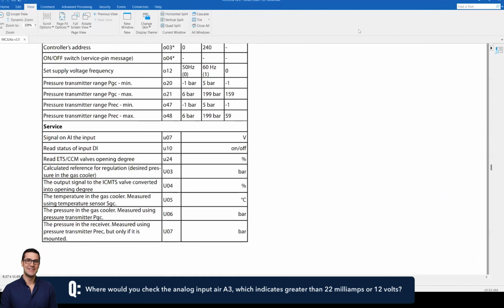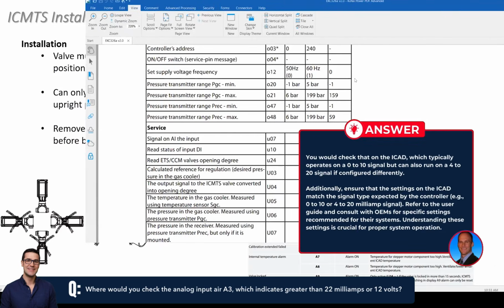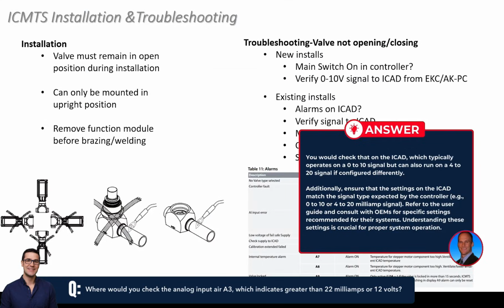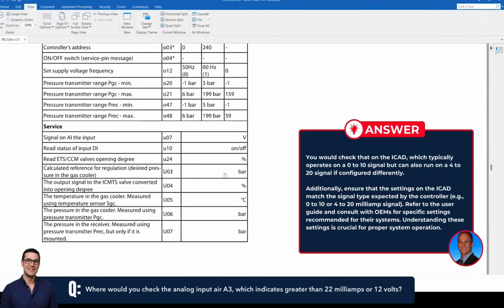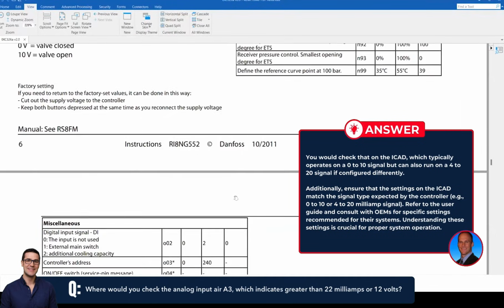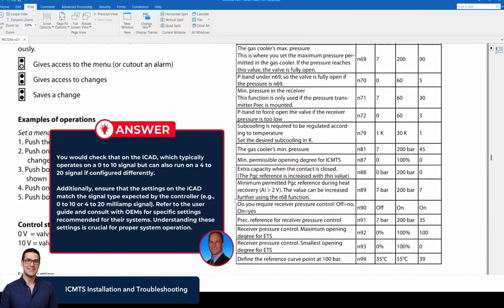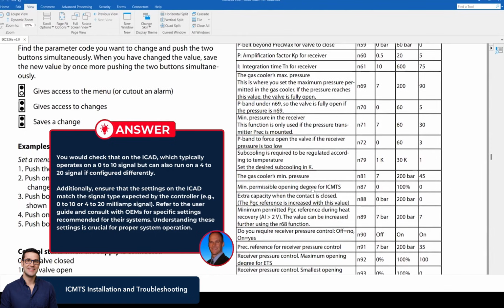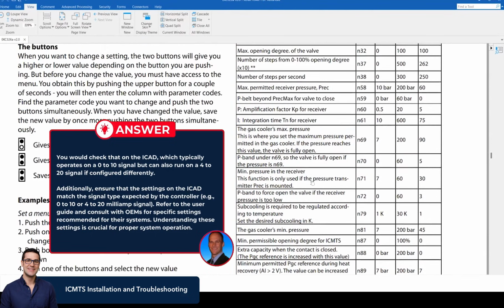So that would be your 0 to 10, or the ICAD does have the option, instead of a 0 to 10 signal, it can run off a 4 to 20 if we have maybe something else driving it other than the EKC. But that's where it also becomes important when you look at the user guide that I'll bring back in here to understand all your settings. And I think the OEMs do a good job of knowing what settings should go in for these. I know a lot of them have documented what numbers they want for their systems. So it's always something you can check with them.